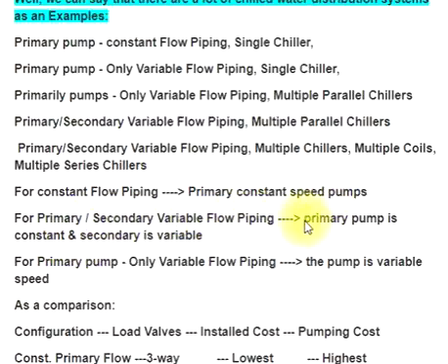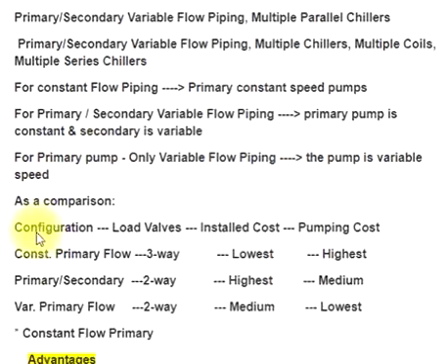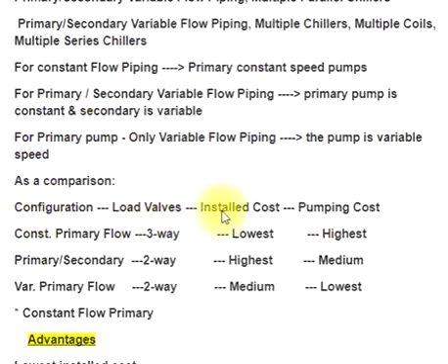Other arrangements include primary constant and secondary variable flow piping, primary pump only with variable flow piping where the pump is variable speed. As a comparison, the configurations are evaluated by load valves, installed cost, and pumping cost.